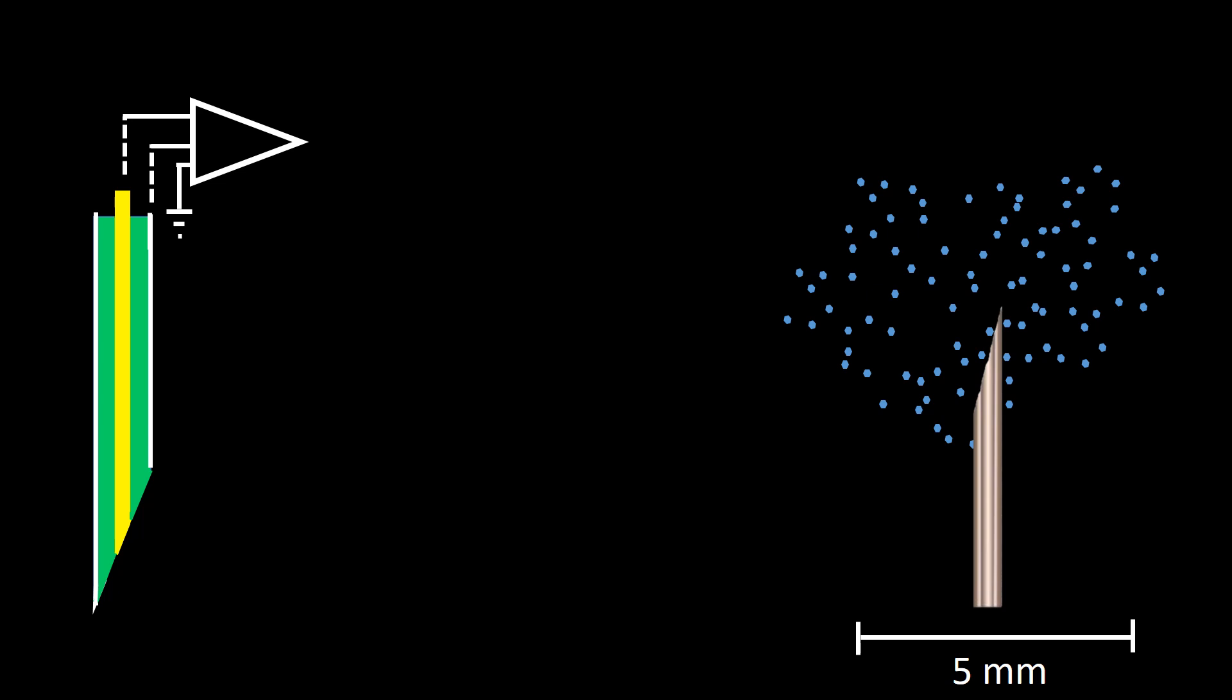A concentric needle is represented here by a relatively thin electrode in yellow separated by insulating material from the shaft that serves as a reference.